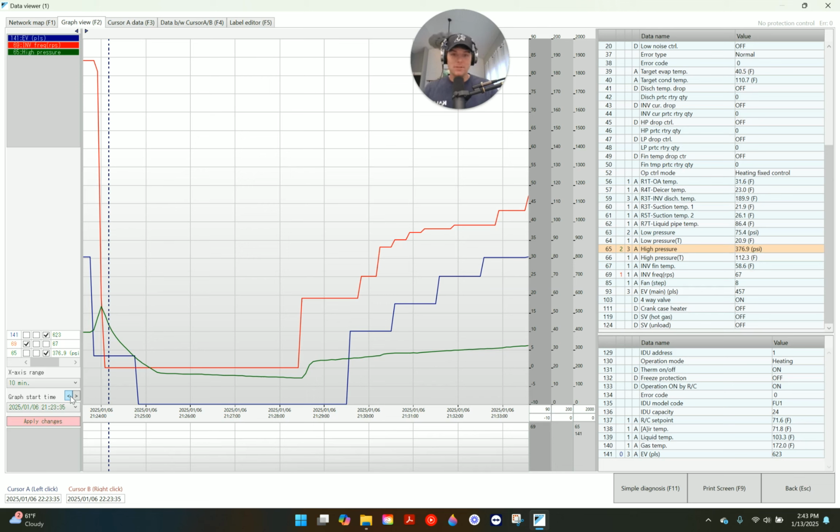Now, this could be 8 ounces, this could be 12 ounces of overcharge, but it's just enough that he only has an issue when it's extremely cold outside. Outside of that, it doesn't operate the way that it would in those low ambient conditions to have that defrost at a constant to where he would hit something like this. So this is a very specific issue where, again, we see the valve pulse to close. That has an immediate effect on the head pressure skyrocketing and the compressor eventually just shutting down altogether to go into restart standby and restart the system altogether.